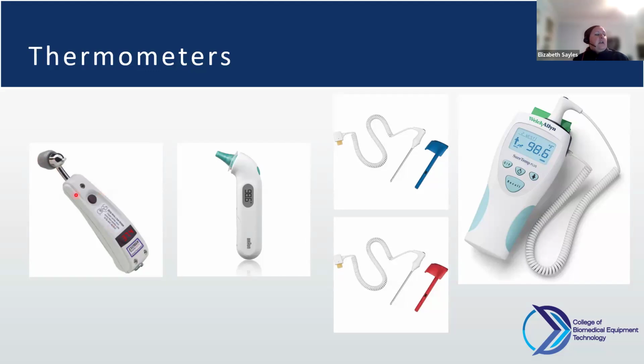If they're off and you've done the cleaning, you've made battery replacements because the battery was low, but there's something else going on with it, usually it's an exchange with Exergen for a full replacement, and if you have an agreement with them, they usually won't charge you for the replacement. Kind of the same thing for the tympanic thermometers. Some of the older tympanic thermometers that I've seen do have a calibration, where they'll have a well that you can calibrate the thermometer to specific temperatures. I think the newer ones tend to be very similar to the temporal scanner, where there's not really a lot we can do from a biomed perspective. We can replace batteries in them, but in terms of verifying the functionality of it and things such as that, there's not really a lot we can do.